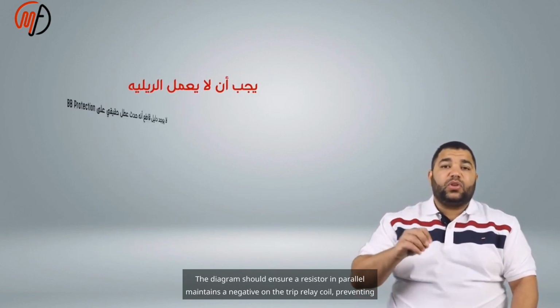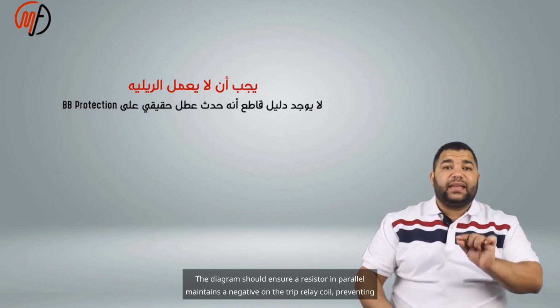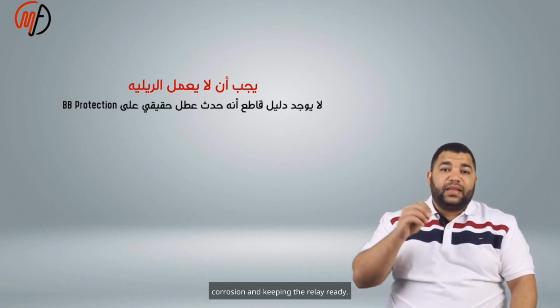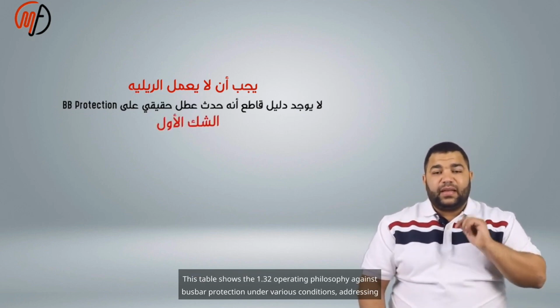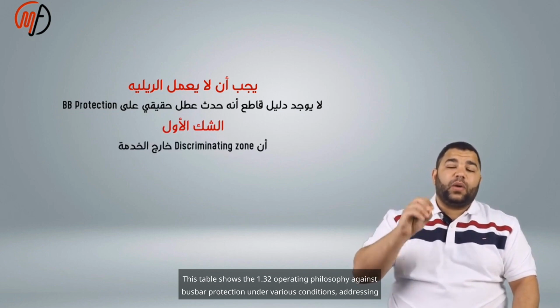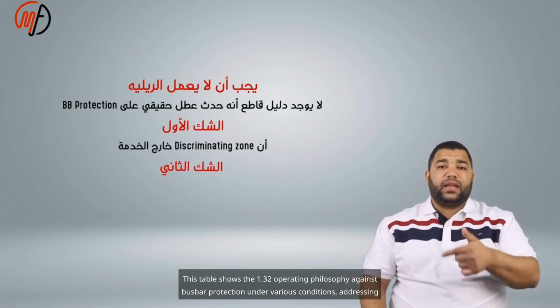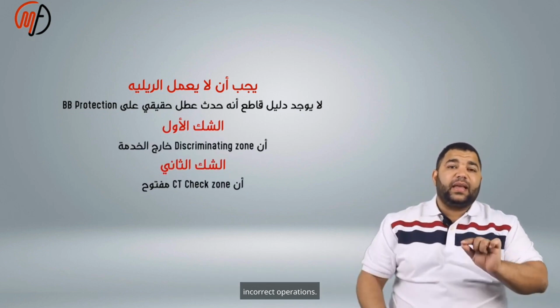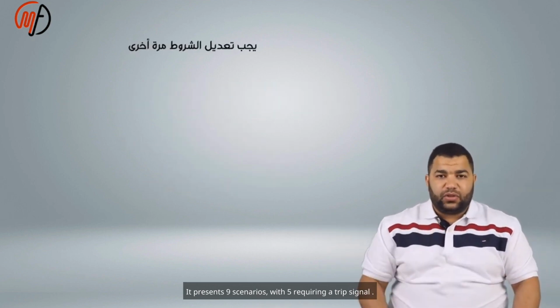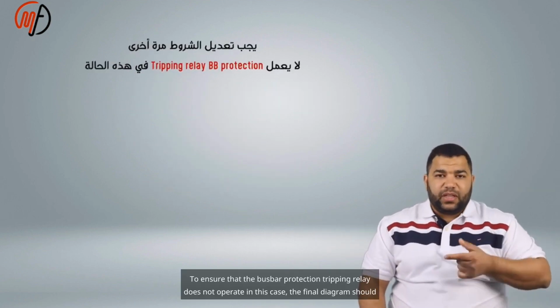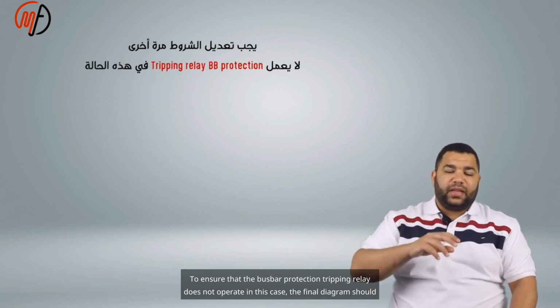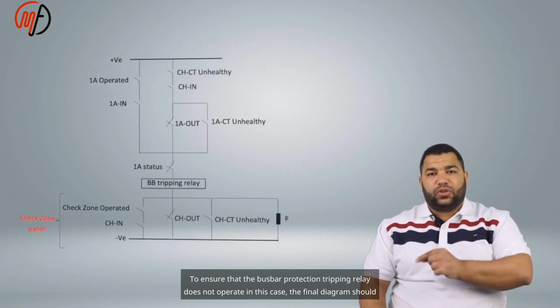The diagram should ensure a resistor in parallel maintains a negative on the trip relay coil, preventing corrosion and keeping the relay ready. To ensure that the busbar protection tripping relay does not operate in this case, the final diagram should look like this.